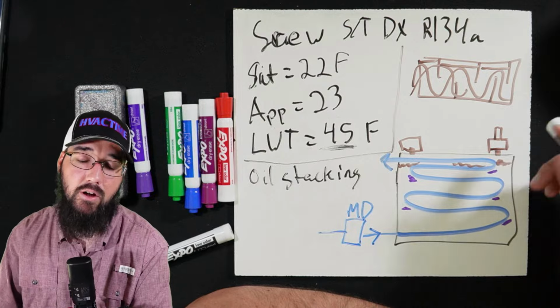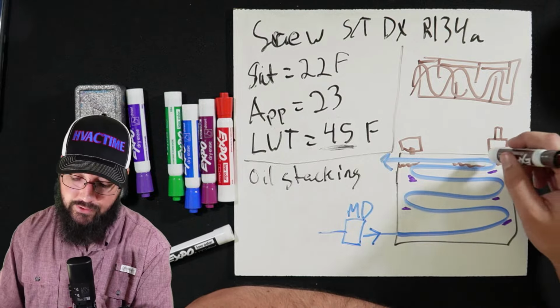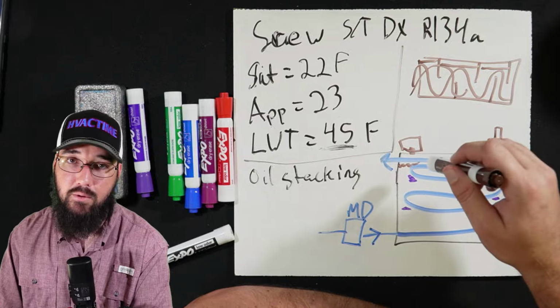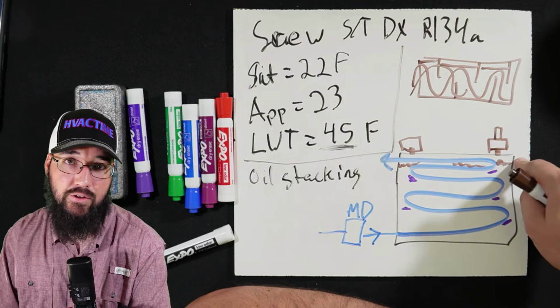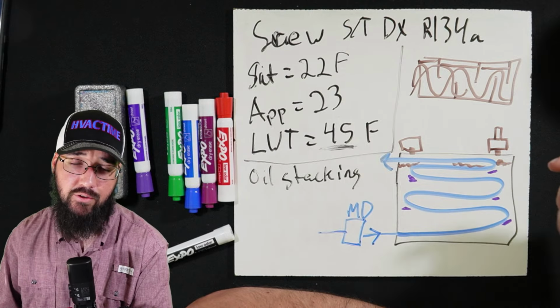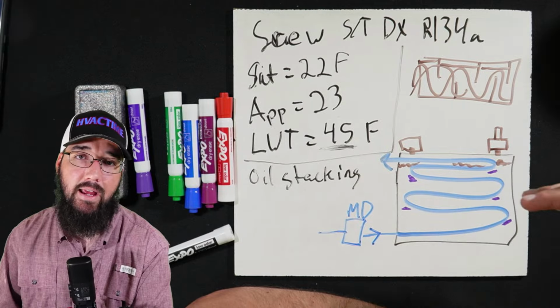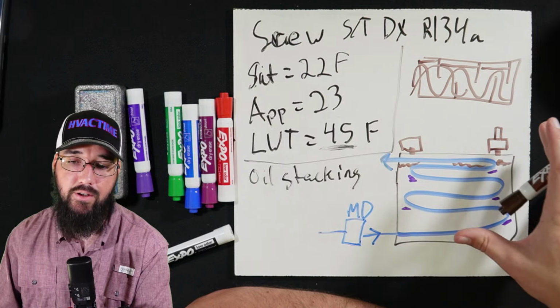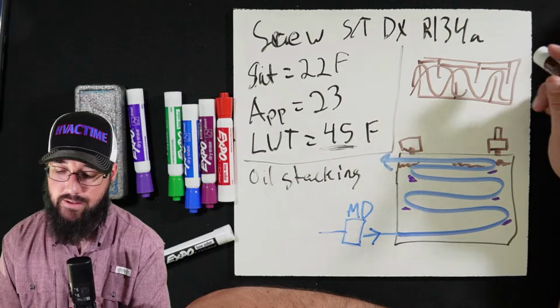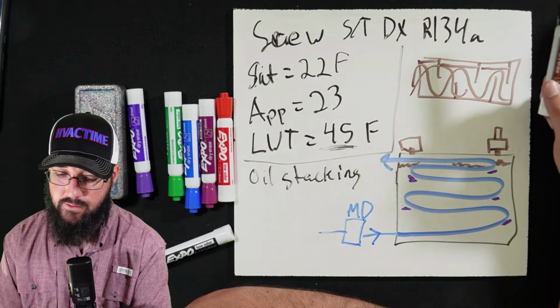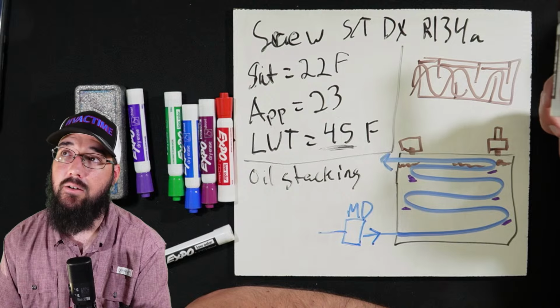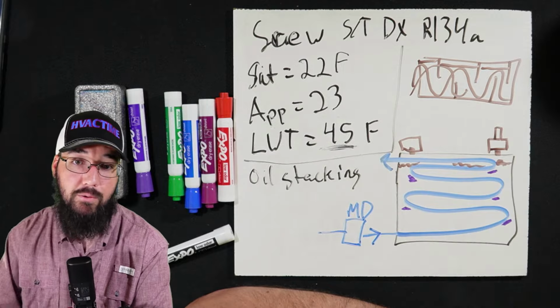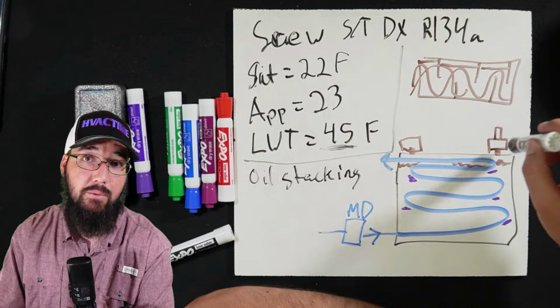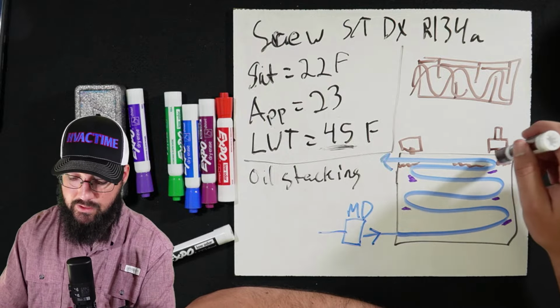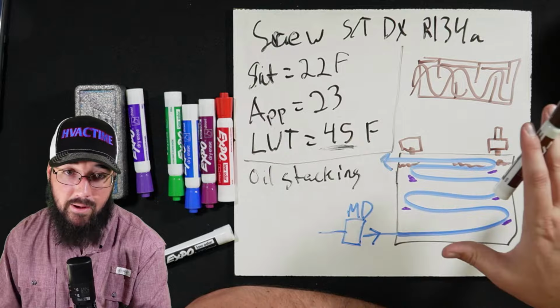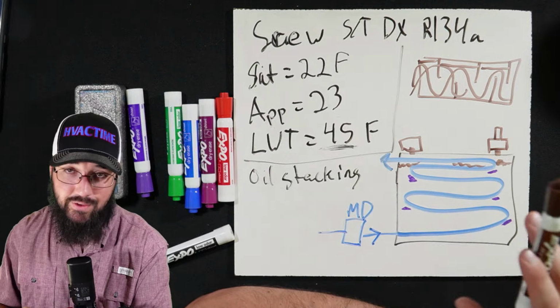Isolate that evaporator, shut the chiller down first, please. Then isolate that evaporator, and even if you just put a ball valve up there, typically these will be a 1/2 inch threadolet that you can thread a valve with a nipple into. If you put a ball valve in there, you can always add an air bleeder later, like a Hoffman bleeder, as long as there's a ball valve there. So I would just suggest start with that, and then see how much air may be in that evaporator. It may not be the problem. It's just an option on the table.